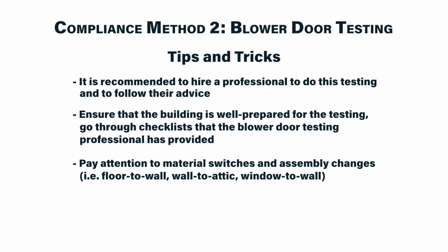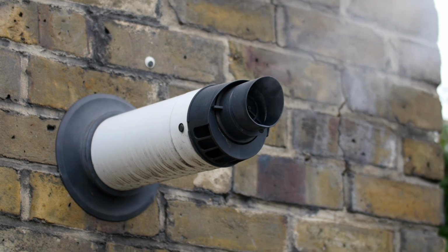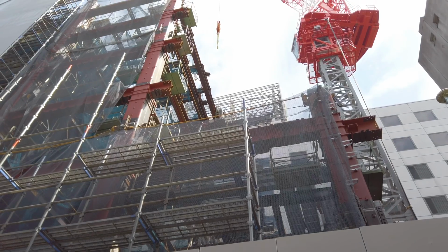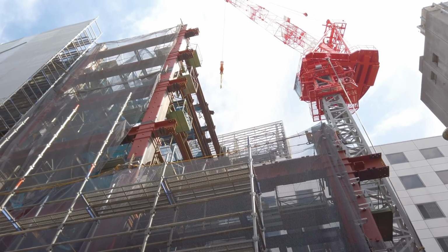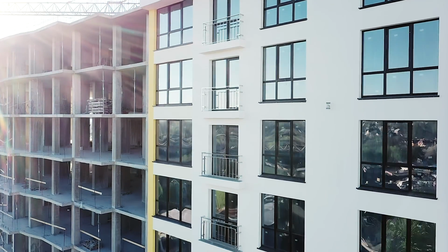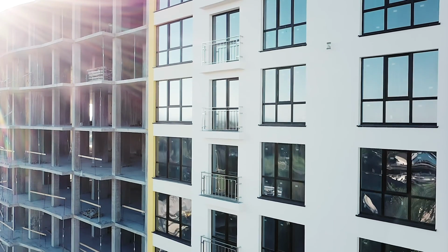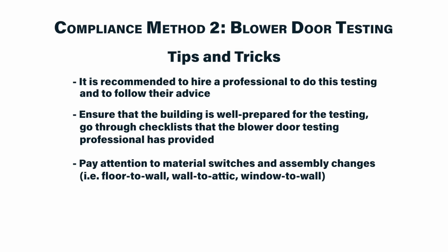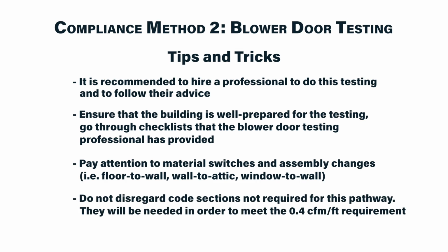This includes spaces where vents or exhaust travel through the building envelope or where envelope construction varies. Second, it is important to pay attention to changes in assembly, such as window-to-wall connections, floor-to-wall connections, or attic-to-wall connections. Finally, even though you are not required to follow all the air sealing sections in IECC 2018, implementing them will help put you on the right track to passing the blower door test.